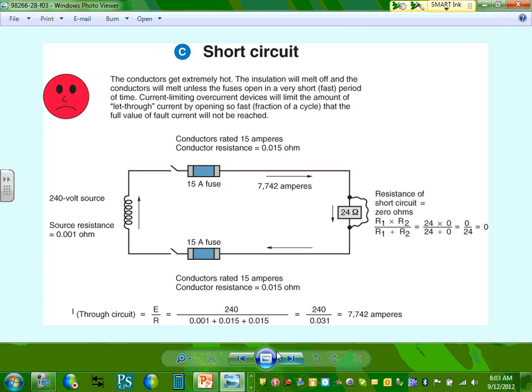Now the short circuit condition, can we pick on you, Jeremy? Jeremy, my friend, went in the circuit right around the heater, and he bypassed the heater. Can you guys see what he did? Right in here. He basically brought phase A and phase B and put them together with a wire nut. That's, we are in a short circuit condition.